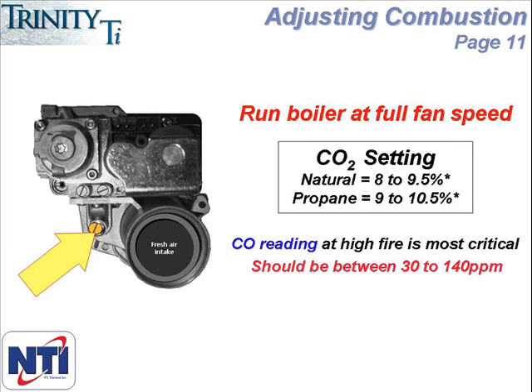Once you've completed the readings at high fire and confirmed that the CO2 and CO readings are both at acceptable levels, you then need to repeat the process at minimum fan speed.